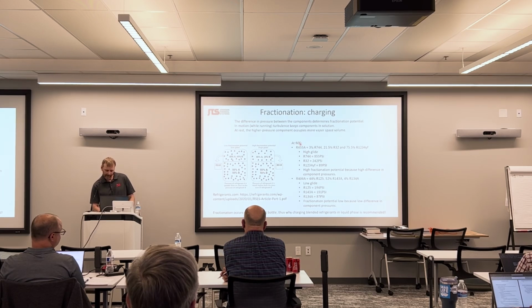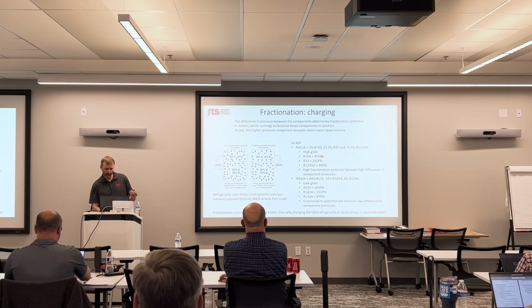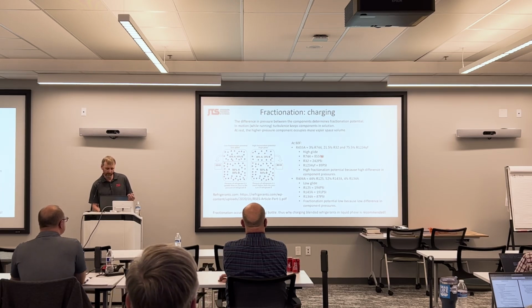So at 80 degrees, the CO2 component has a pressure of 955 psi. The R32 component has a pressure of 232 psi. And the R1234YF component has a pressure of 89 psi. The difference in pressure between these is great. Therefore, one would expect that this refrigerant would have a very high glide and very high fractionation potential.